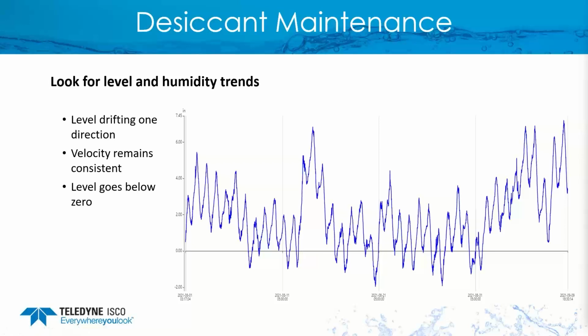And so one way to test this is you can take your sensor, put it in a bucket of water. It's going to have a constant level minus a little bit of evaporation. But throughout the day, as the barometric pressure changes, you would actually see the level increase and decrease with that pressure because it doesn't have the referenced atmosphere. And so that's usually an indication that the desiccant does need to be replaced.